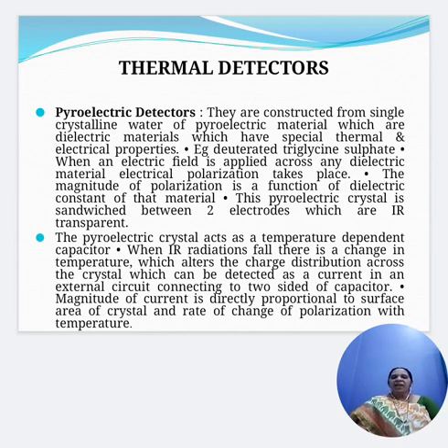This pyroelectric crystal is sandwiched between two electrodes which are IR transparent. The pyroelectric crystals act as temperature dependent capacitors. When IR radiation falls, there is a change in the temperature which alters the charge distribution across the crystal, which can be detected as a current in an external circuit connecting the two sides of the capacitor.